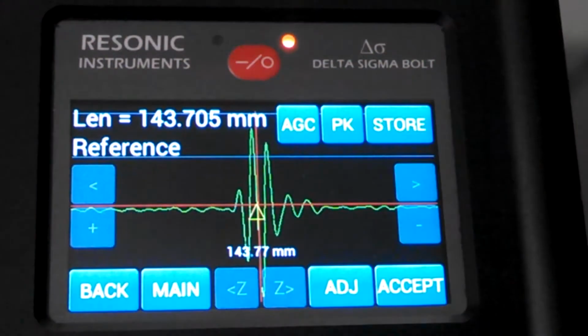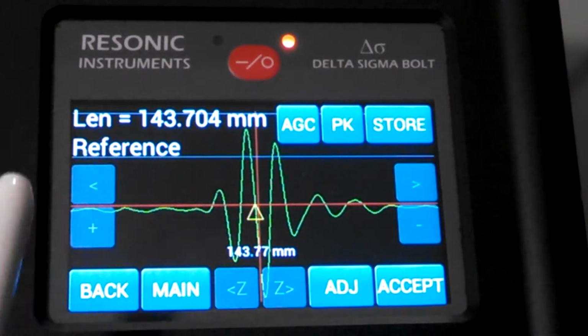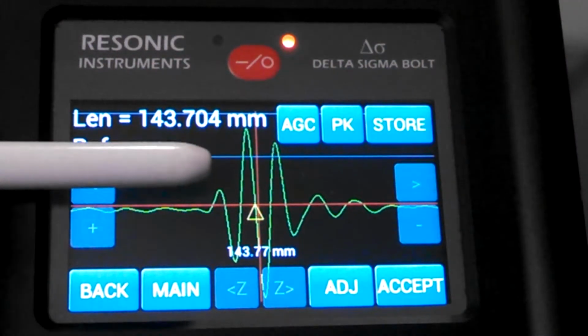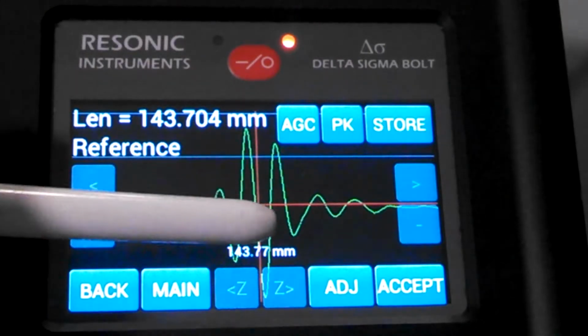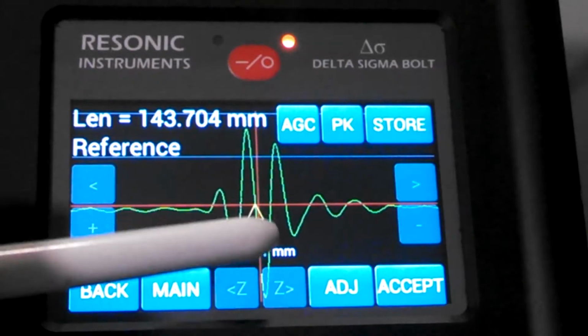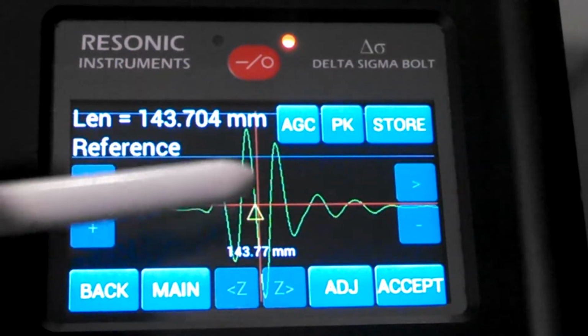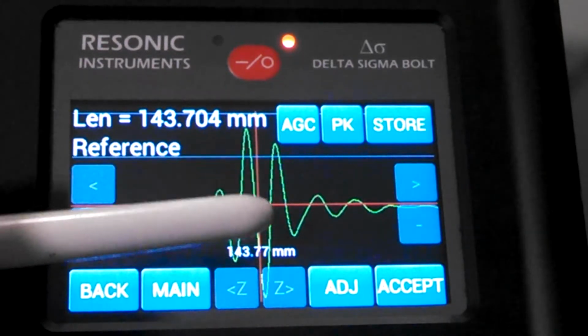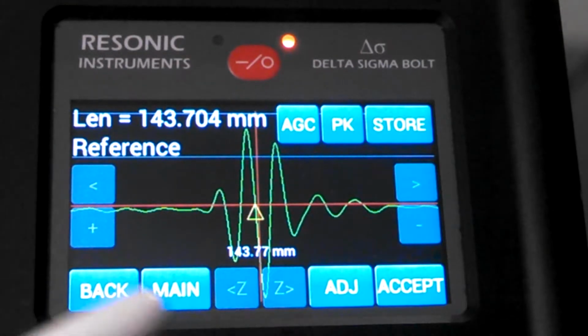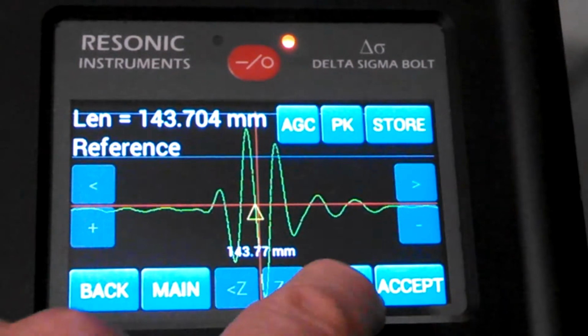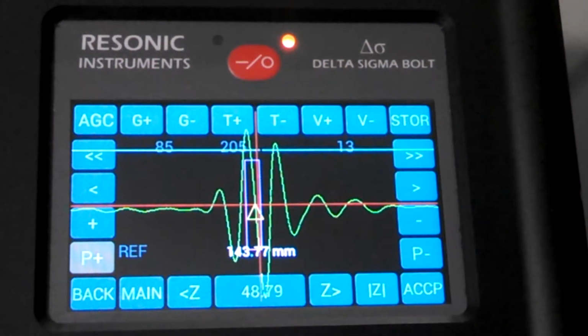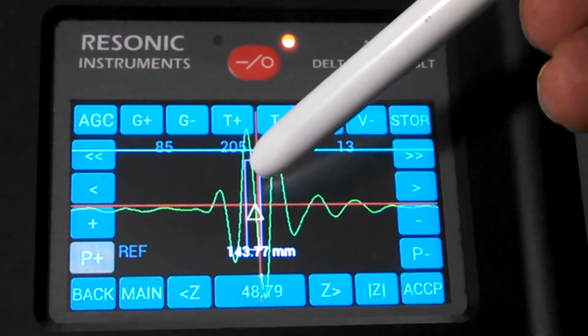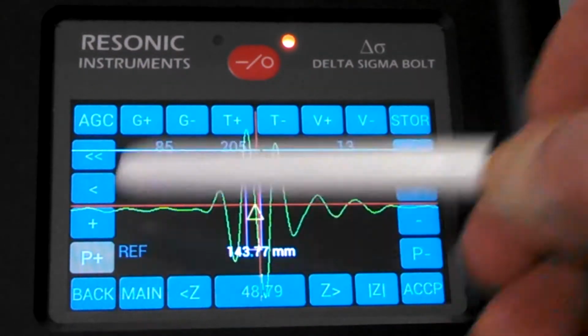Now we'll go take a look at the scope. Nice signal, 5 megahertz, within the parameters of the receiver, not a problem. Now you can see that the threshold is up here somewhere, and we're triggering on the zero crossing on the falling wave, so we have a positive polarity signal. The DS1 has chosen the positive polarity and the threshold to trigger on the zero crossing. If we hit adjust, we go into the manual receiver setting. Here the blue box shows you where the signal zero crossing is. The positive polarity is lit up red. The negative polarity is not.